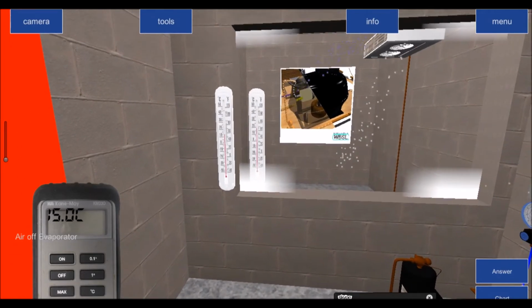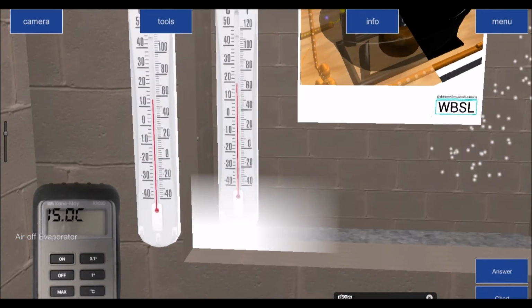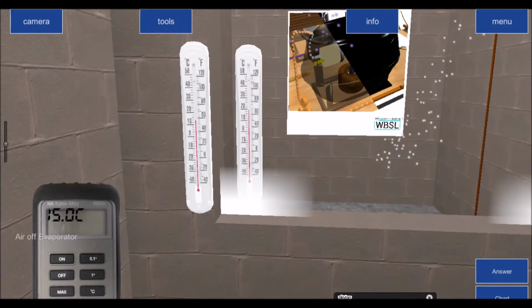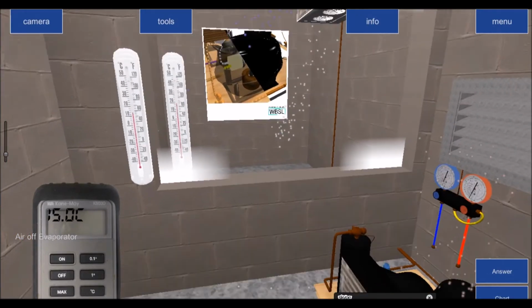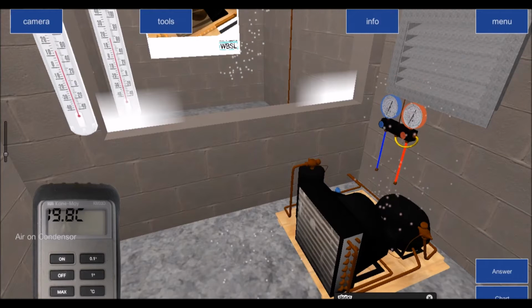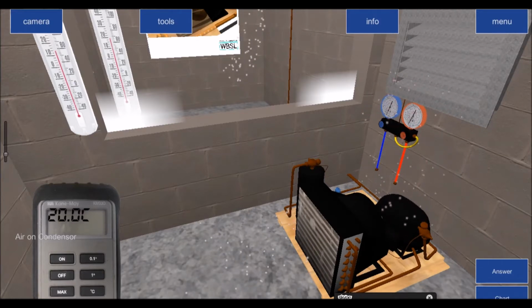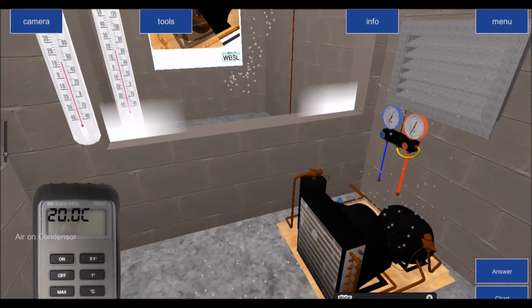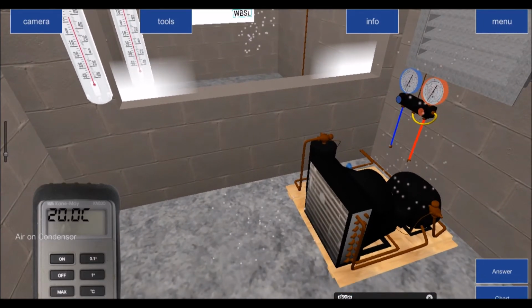One of the things you will notice here is the room temperature that the condenser is located in. You can see it's about 10, 11, about 12 degrees Celsius. So that's the room temperature. But if I get my good thermometer and put it to the face of the condenser, we can see that the air coming onto this condenser is plus 20 degrees. Now we need to determine the temperature of the refrigerant inside the condenser. Remember, we have a desuperheating zone, and the very top of the condenser is the desuperheating zone.